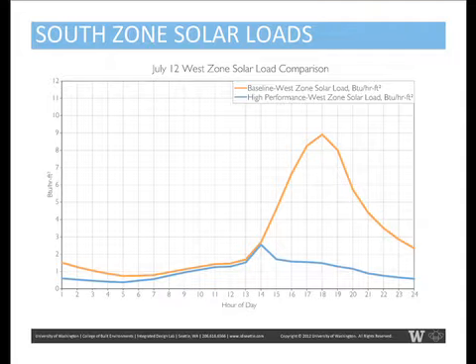And why that's important is because the chilled ceiling panels, radiant chilled panels, can't accommodate that kind of peak load. And so we need to lop that off, not to mention the displacement ventilation wouldn't work. As all mechanical engineers and facility operators would tell you, there's a horrible chasing-your-tail thing going on here. When you have chilled water at roughly the same temperature all the time, you can't chill it more as it gets hotter during the day.